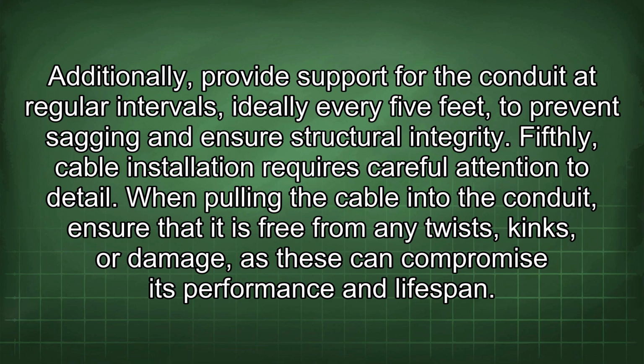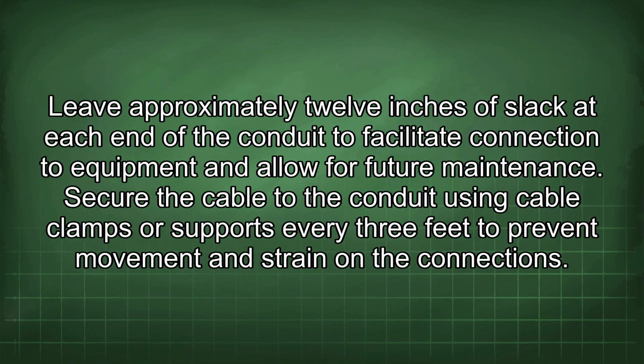Fifthly, cable installation requires careful attention to detail. When pulling the cable into the conduit, ensure that it is free from any twists, kinks, or damage, as these can compromise its performance and lifespan. Leave approximately 12 inches of slack at each end of the conduit to facilitate connection to equipment and allow for future maintenance.